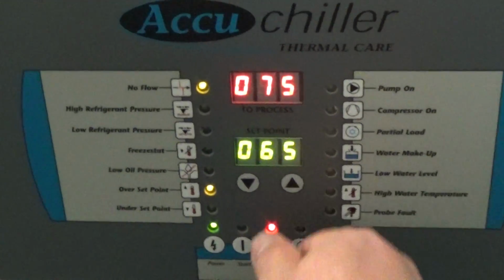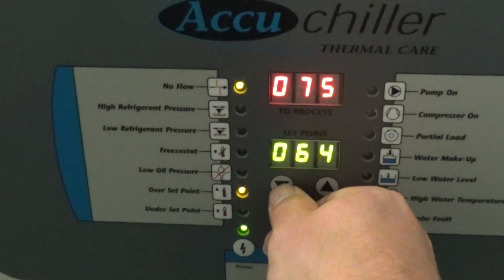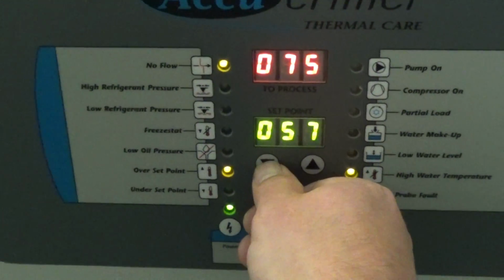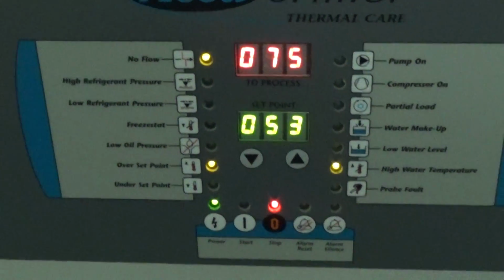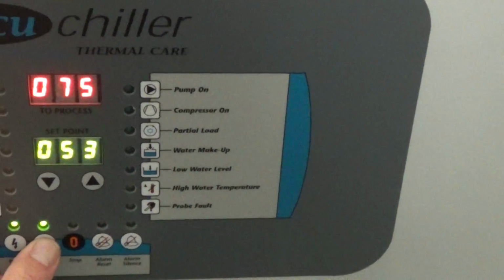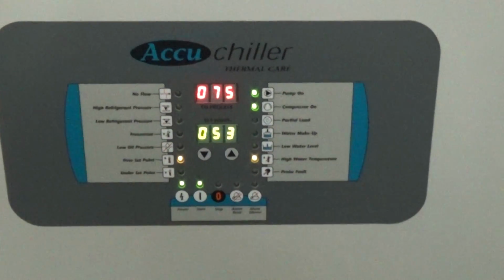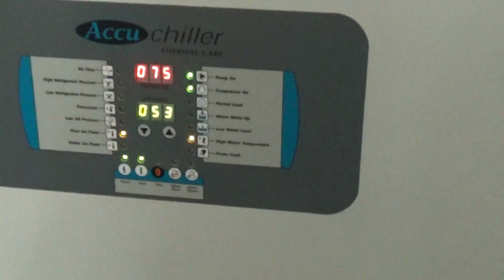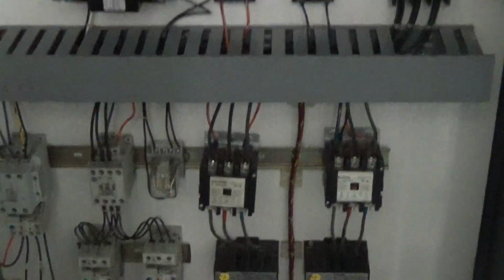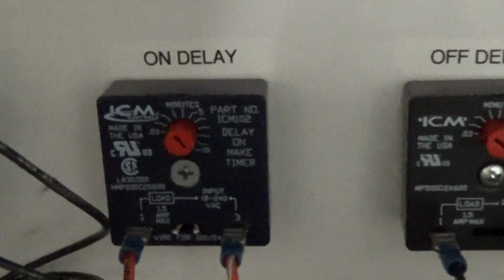So with straight water, I don't want to have a set point for this unit, if you're running straight water, below 53. And right now, the unit does start. So the first thing that happened is one of the compressors came on, and both fans. And we'll label the contactors here, but this contactor's pulled in. This one's not going to pull in to cool down until our compressor on delay kicks in.